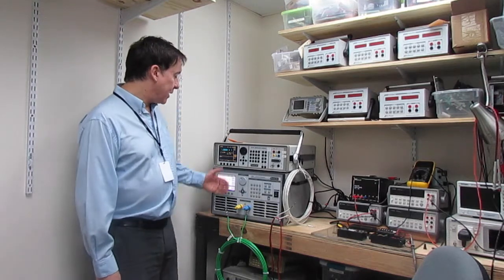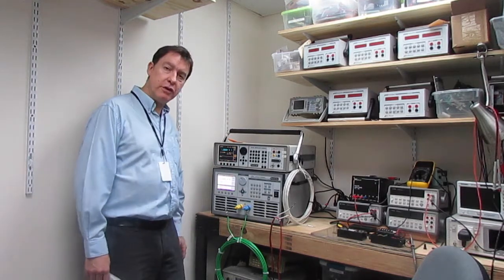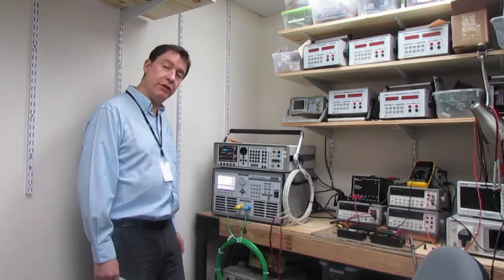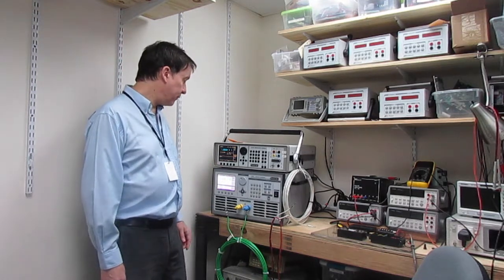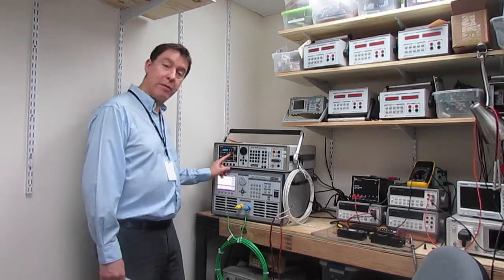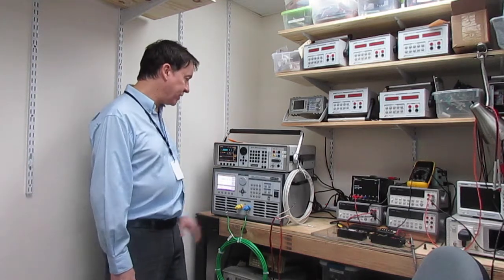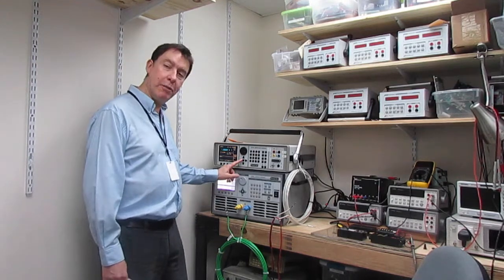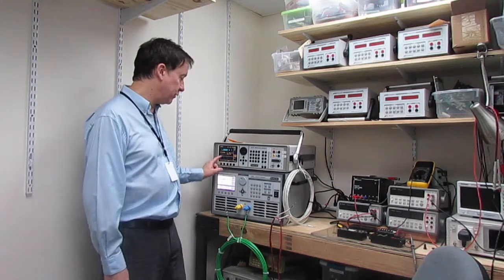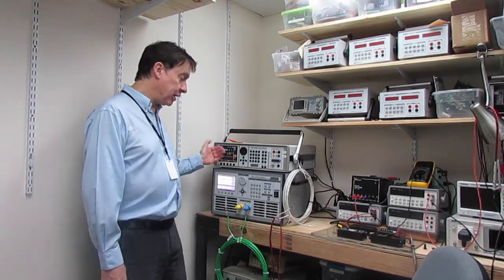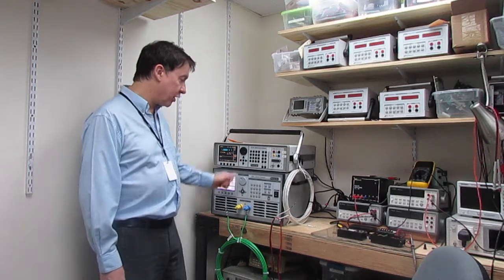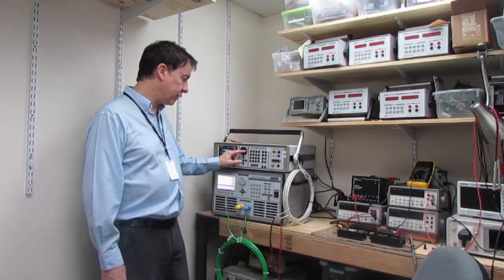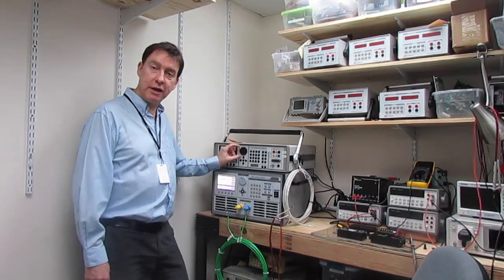Looking at the calibrator, we have a screen there that shows you the present function that's enabled, the value, the frequency, the type of waveform that's coming out. It's all in this status screen. We have a spin wheel and up and down keys which allow the user to actually change any of the values, and you can do it in increments or type in the value or even just rotate the actual parameter using the spin wheel.